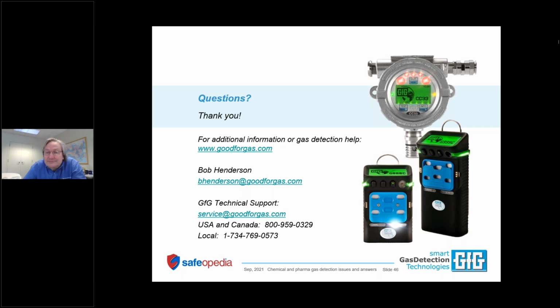Why is alcohol so hard to detect with a standard LEL sensor? Well, for a couple of reasons. One is the standard LEL sensor is protected by filters and flame arrestors, and there are barriers for the alcohol that the alcohol has to diffuse through before it can get into the sensor and finally get oxidized on the active bead. So it just takes time to get there.